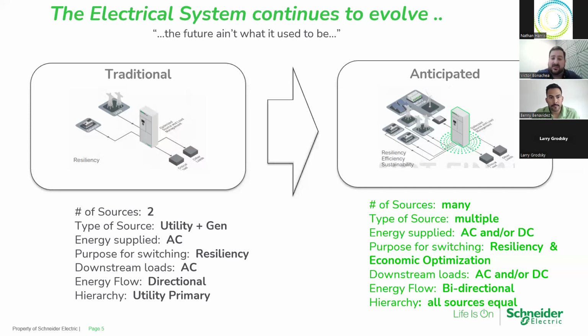And when it is a source, it's not necessarily always on the top of your power distribution system. It could be on the bottom, where traditionally you've seen loads, and that changes the dynamic because now the energy can flow in both directions. The energy isn't just flowing from the top, from your sources, down to your loads. It could be flowing back up through your power distribution system to feed loads that are higher up in your distribution, or potentially even selling back to the utility if you have that kind of agreement with your local utility company.